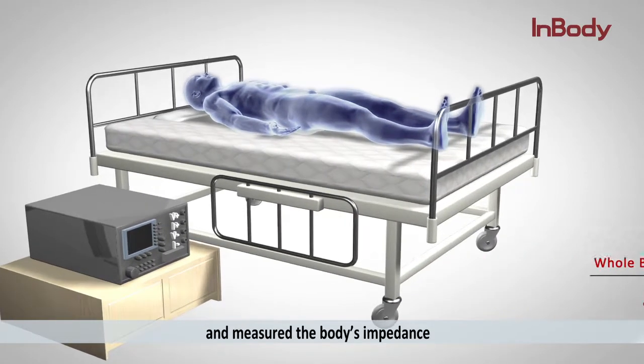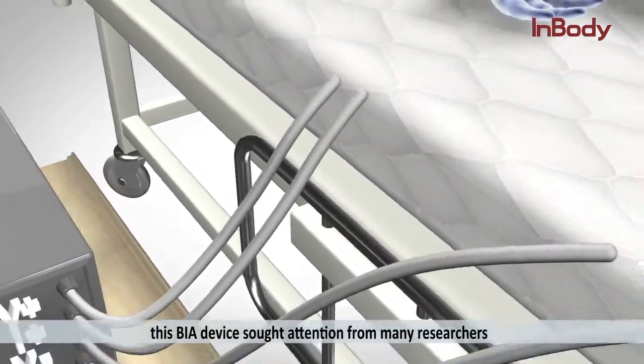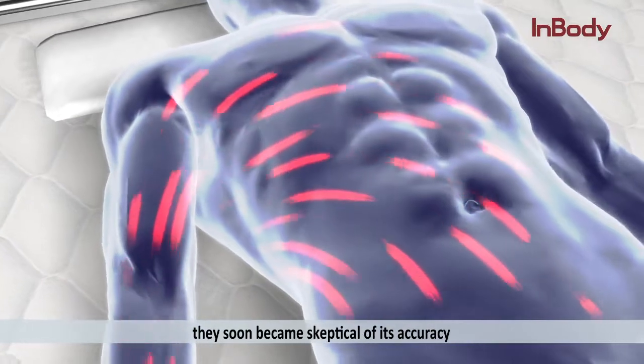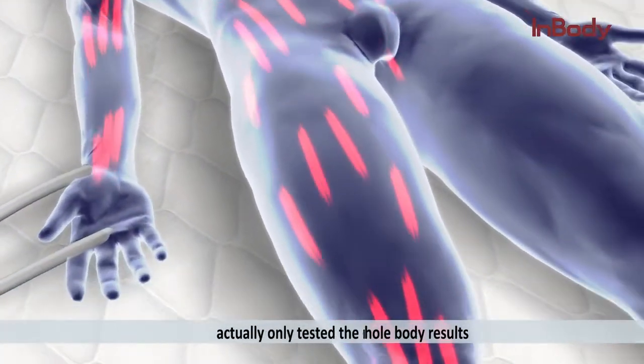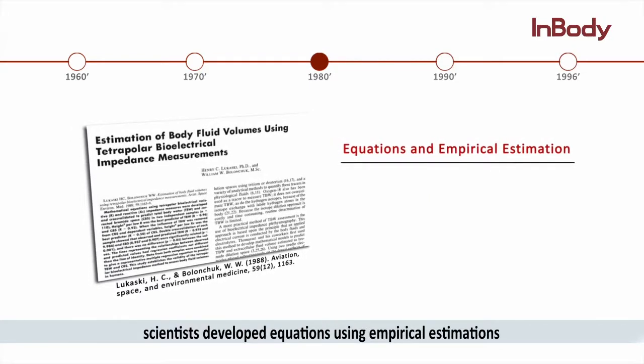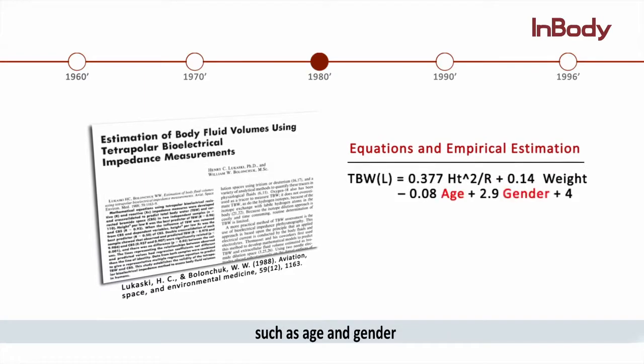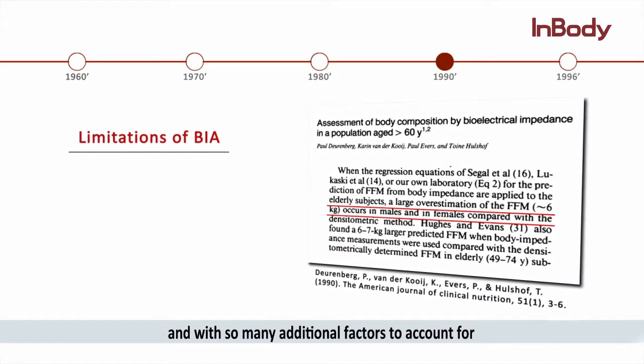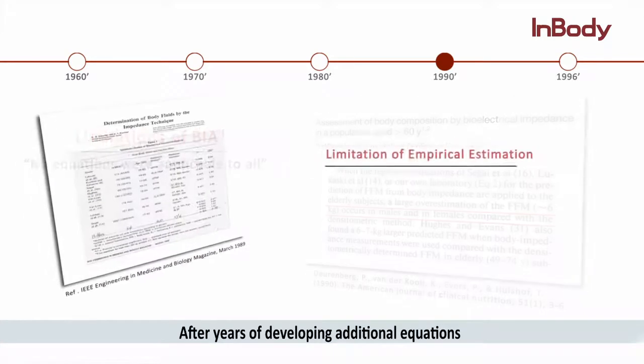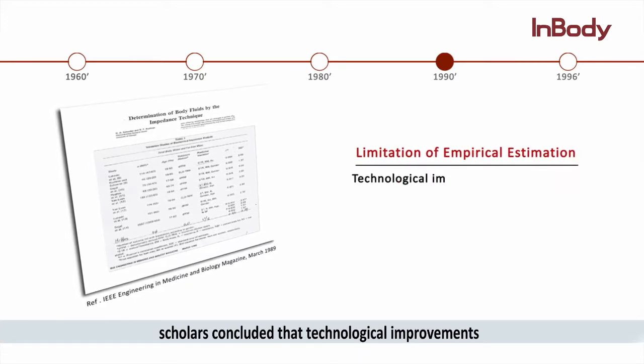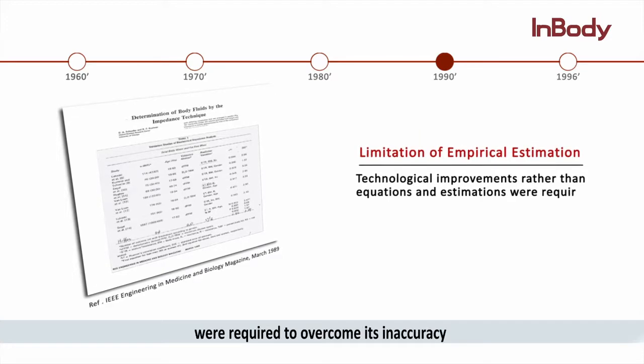Due to its simplicity and convenience, this BIA device attracted attention from many researchers. However, as more researchers started using the device, they soon became skeptical of its accuracy. The devices claimed to produce whole-body results but actually only tested the right half of the body, and their use of a single low frequency inaccurately measured whole-body impedance. To compensate, scientists developed equations using empirical estimations such as age and gender, but the equations were only specific to their test groups. With so many additional factors to account for, no equations were applicable to all. Scholars ultimately concluded that technological improvements — rather than equations and estimations — were required to overcome this inaccuracy.